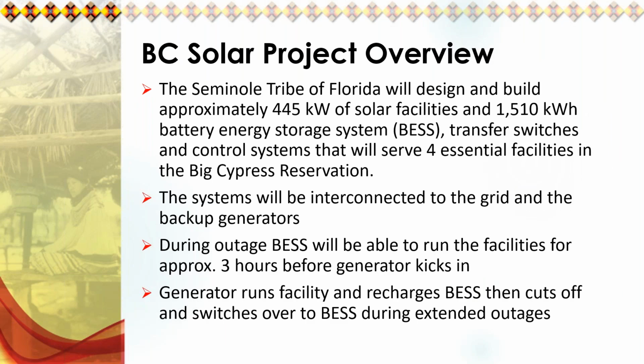So here's an overview of our BC solar project. The tribe will design and build approximately 445 kilowatts of solar PV facilities and a 1,510 kilowatt-hour battery energy storage system, otherwise known as BESS, transfer switches and control systems that will serve four essential facilities in the Big Cypress Reservation. The systems will be interconnected to the grid and to the backup generators. During an outage, the BESS will be able to run the facilities for approximately 3 hours before the generator kicks in. The generator will run the facility and recharge the BESS, then cut off and switch back to the BESS when it reaches a certain level of charge in the case of an extended outage.